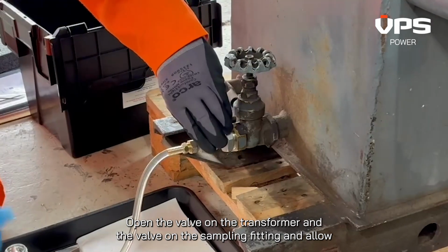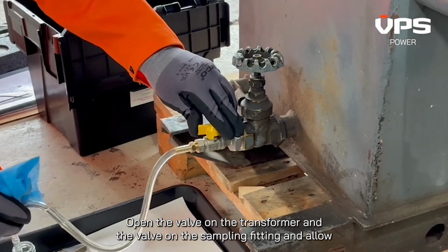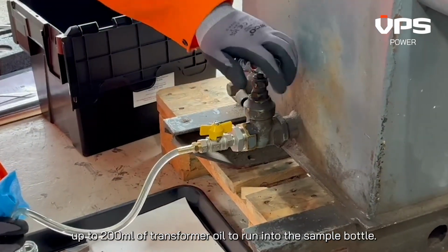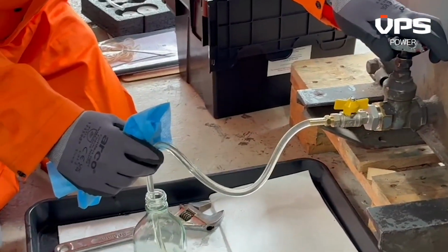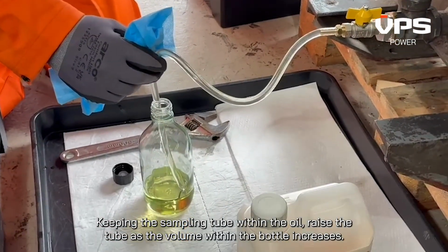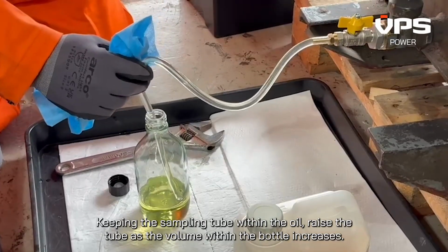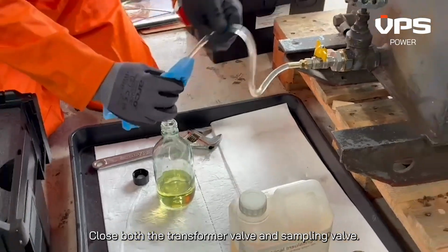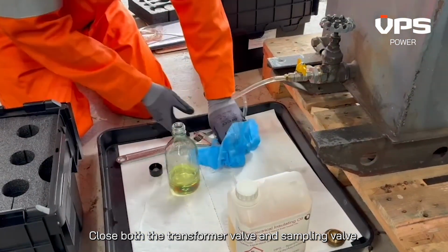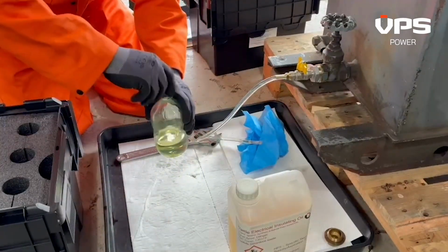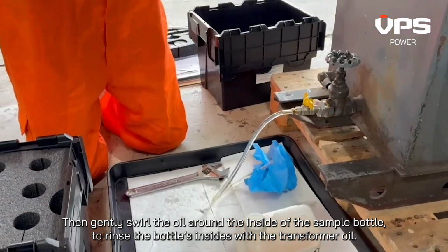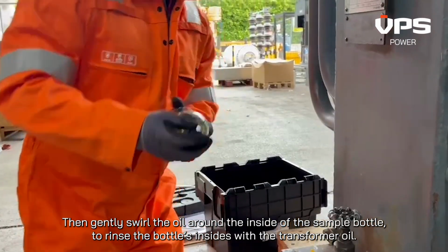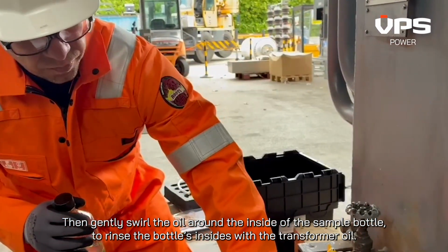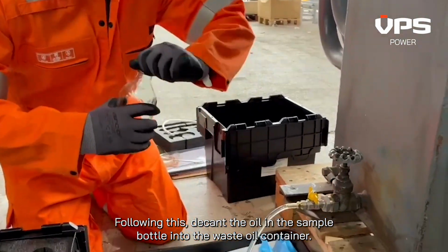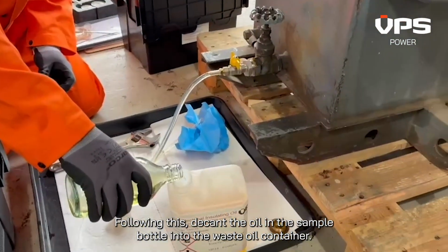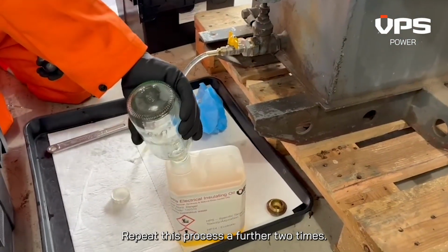Open the valve on the transformer and the valve on the sampling fitting and allow up to 200 ml of transformer oil to run into the sample bottle. Keeping the sampling tube within the oil, raise the tube as the volume within the bottle increases. Close both the transformer valve and sampling valve. Place the cap on the sample bottle, then gently swirl the oil around the inside of the sample bottle to rinse the bottle's insides with the transformer oil. Following this, decant the oil in the sample bottle into the waste oil container. Repeat this process a further 2 times.